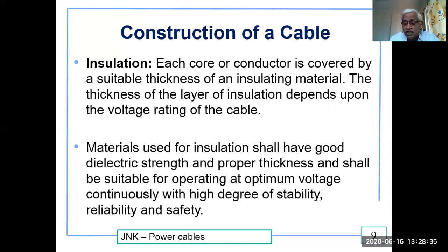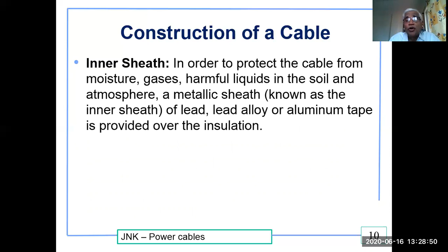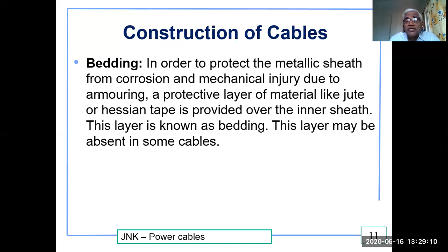Inner sheath. In order to protect the cable from moisture, gases, and harmful liquids in the soil and atmosphere, a metallic sheath known as an inner sheath of lead, a lead alloy or aluminum tape is provided over the insulation. Bedding. In order to protect the metallic sheath from corrosion and mechanical injury due to the armor, a protective layer of material like jute or hessian tape is provided over the inner sheath. This layer is known as bedding. This layer may be absent in some cables.